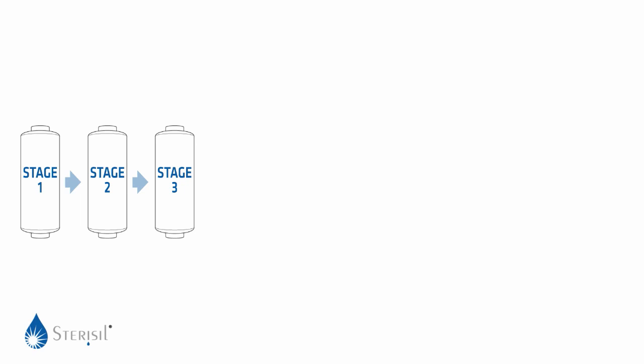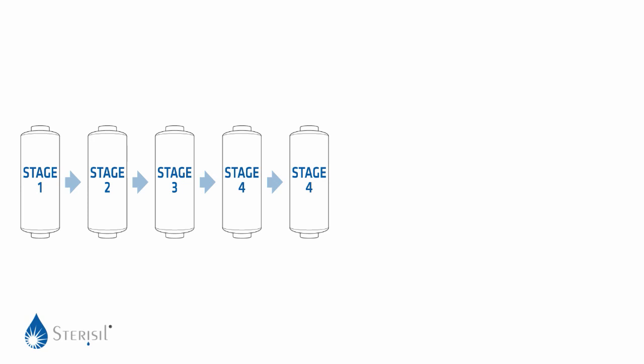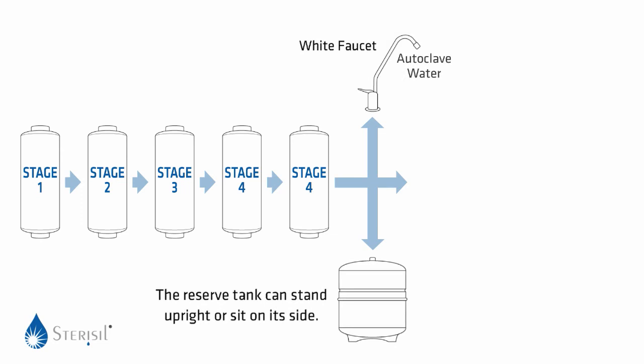Here's how the Sterisil system works. Stages 1, 2, and 3 remove particulates such as dirt and rust as well as 90% of all total dissolved solids, TDS — including everything from organic pesticides and solvents to elements such as chlorine and lead. The two Stage 4 cartridges further remove any remaining TDS from the water to produce distilled or deionized quality water for autoclaves. Sterisil autoclave water is five parts per million, as required for autoclaves.